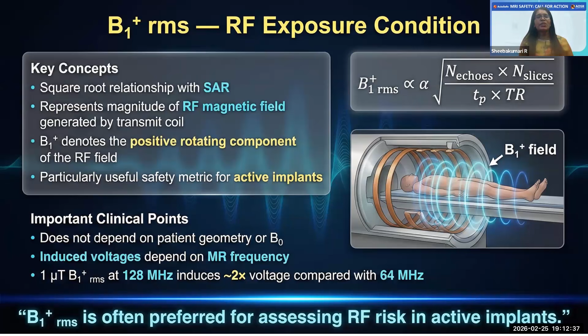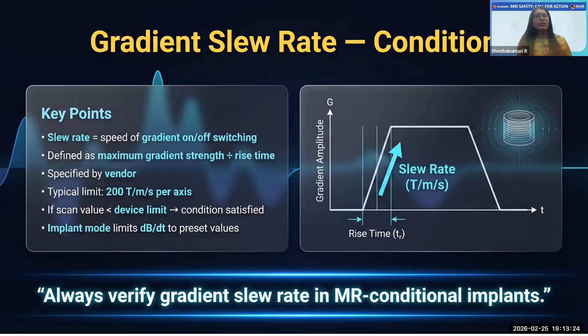Slew rate means how fast we are switching our gradient on and off. The maximum slew rate of most implant scanners is limited to 200 Tesla per meter per second. Whenever we are scanning a patient with an implant, we can select the normal gradient operating mode or the implant mode, so that the gradient switching is limited to a preset value.